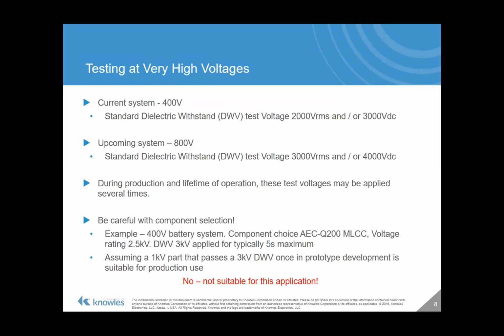So the current system, 400 volts, we are routinely seeing our customers testing these circuits at 2000 volts AC, typically 50, 60 hertz, and 3000 volts DC. Upcoming systems, we're going to go up to 3000 volts AC, 4000 volts DC. And bear in mind that this is not a one-time operation. This is not going to do it in the factory and that's it.